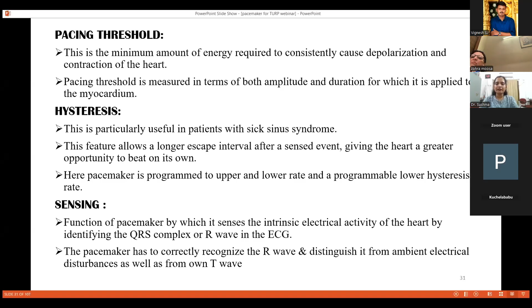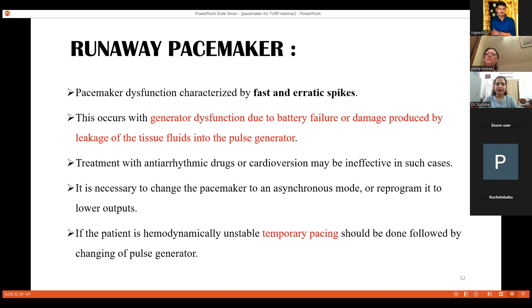Next comes runaway pacemaker. This dysfunction is characterized by fast and erratic spikes. This occurs generally with generator dysfunction, which can be due to low battery life or battery failure or damage produced by leakage of tissue fluids into the pulse generator. Treatment with antiarrhythmic drugs or cardioversion will not be effective in this case. It is necessary to change the pacemaker to an asynchronous mode or reprogram it to lower outputs. If the patient is hemodynamically unstable, then temporary pacing must be done.